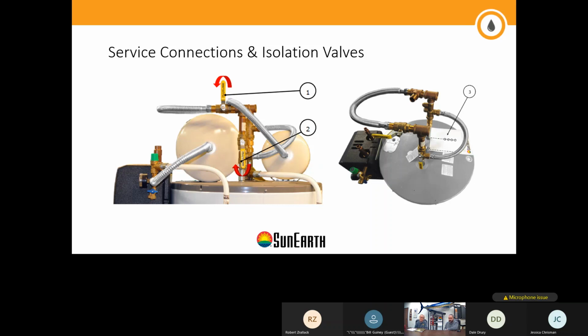So, another thing that will come up for the collectors, and definitely for the tank and the auxiliary unit, is service connection and isolation valves. Personally, one of the most interesting things I saw in a commercial project not too long ago was an inspector who required a set of isolation valves on each individual collector within the array. So each individual collector had isolation valves so it could be completely isolated, taken out and serviced.